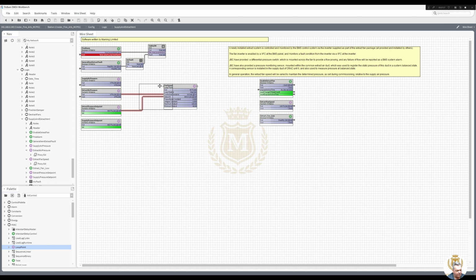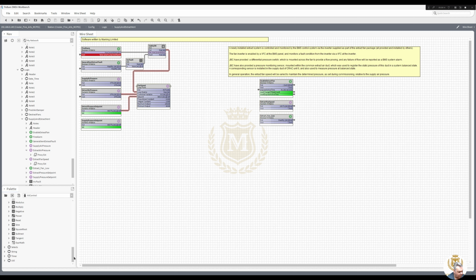Now I only need that enabled. I don't want to put that directly to there, because I only want that to have a value once we are happy that that is on. Loop enabled. Otherwise, when loop is not enabled, that's still going to give 40% out, i.e. the minimum. But I don't know how that system works. For all I know, we've got an enable, we could also work on a fan speed. Sometimes people write logic and say, okay, well, we've got a fan speed of 40, we will run the fan. I don't know. I have not been on site or commissioned it. So because I don't know, I am going to make sure that when we haven't got a signal, we are at 0.